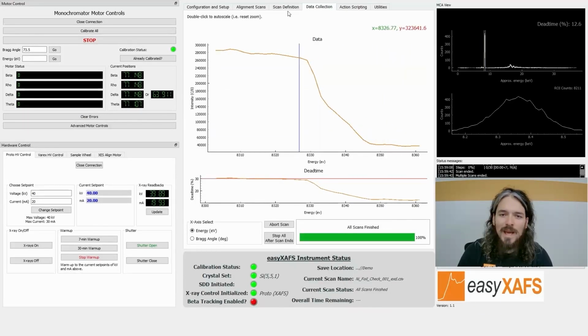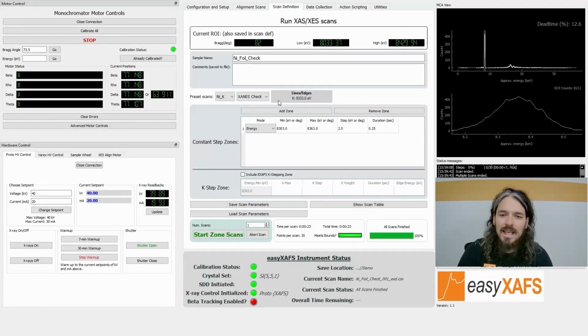Now I could go back to the scan definition tab, and if I change the preset scan type to XANES, you can see that gives us 3 scan zones. We would have coarser steps in the pre-edge region, finer steps around the edge with a longer measurement time, and then coarse steps after the edge region. The default is around 15 minutes, but we've got some good samples here and we've got the system optimized, so we're going to be able to do the demonstration measurements with just 1.5 minutes per sample.